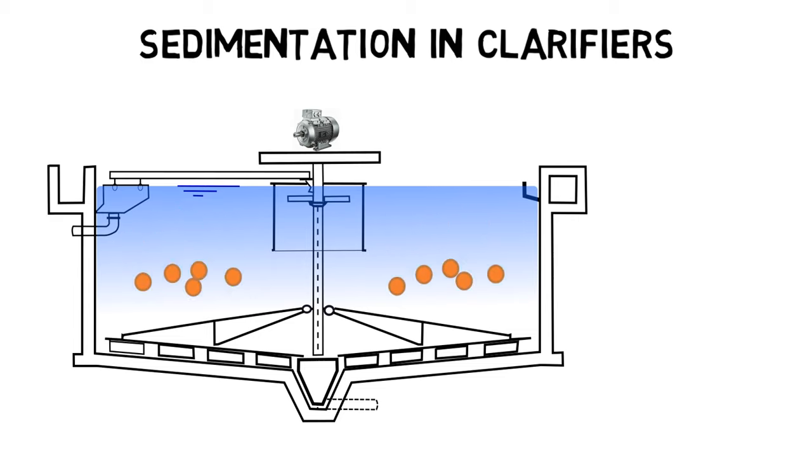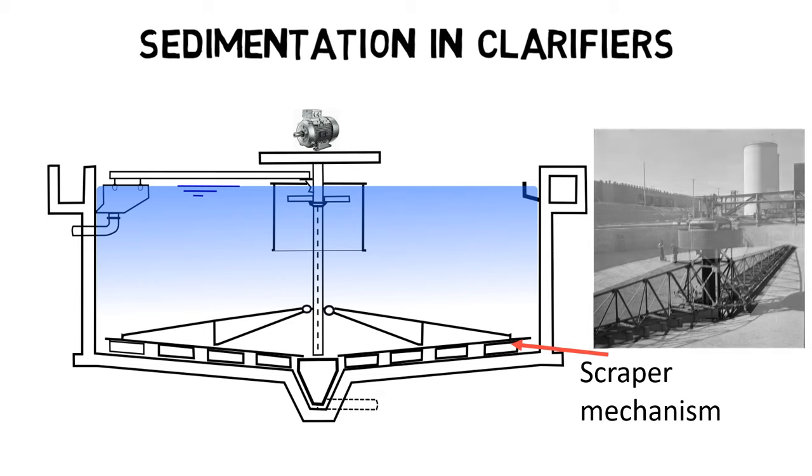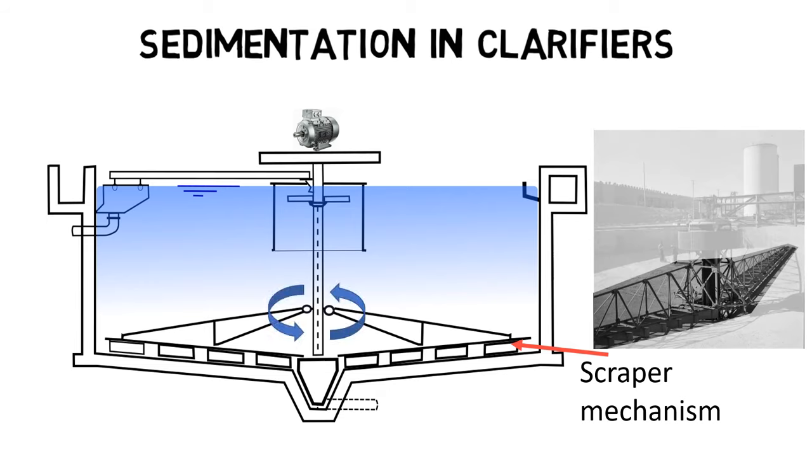Inside the clarifier, solid contaminants will settle down to the bottom of the tank where they are collected by a scraper mechanism and removed by another centrally located pipe. The scraper mechanism arms rotate slowly along the clarifier's perimeter and are attached to a centrally located shaft which is powered by a drive system on the clarifier bridge.